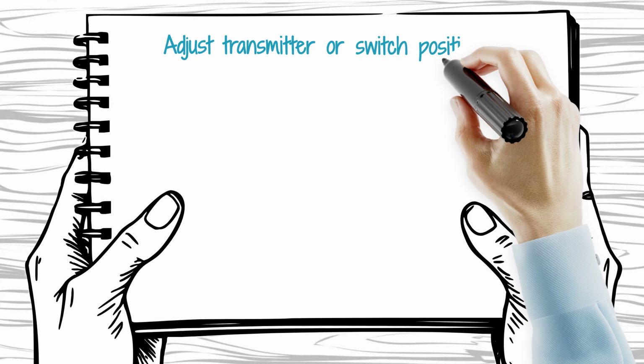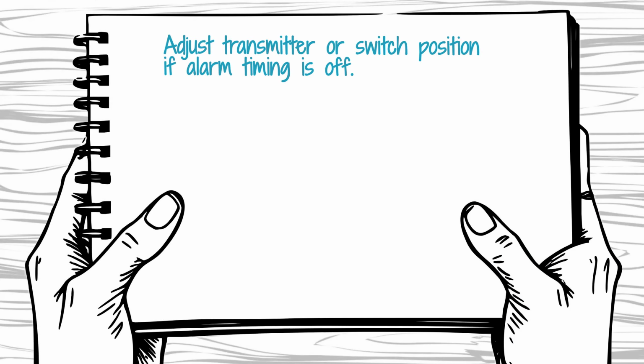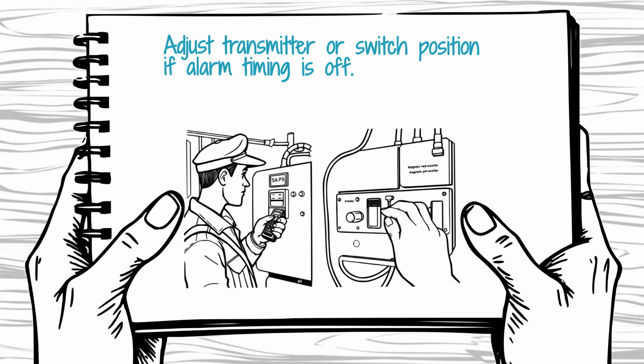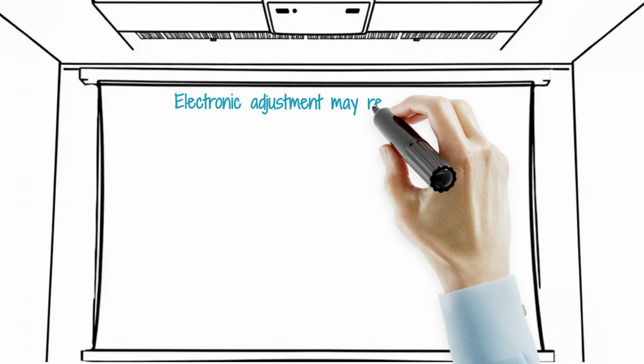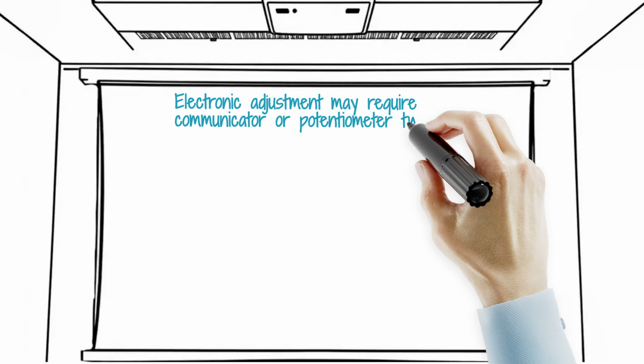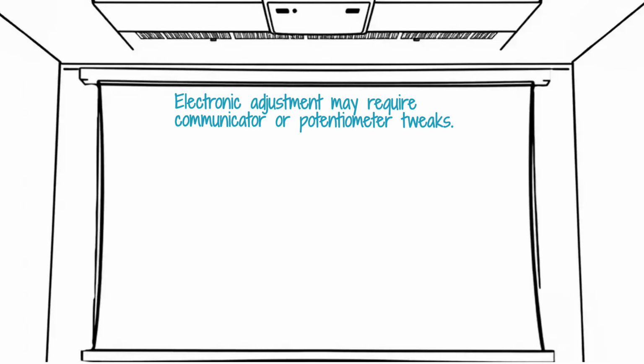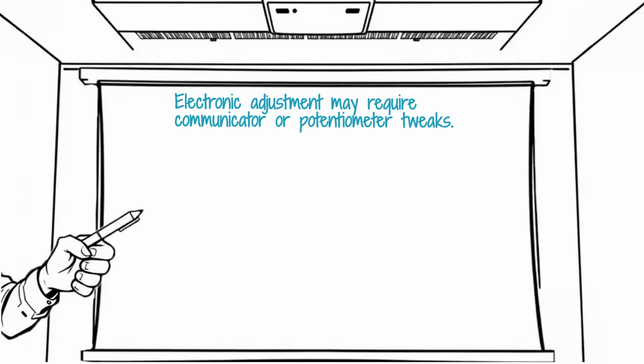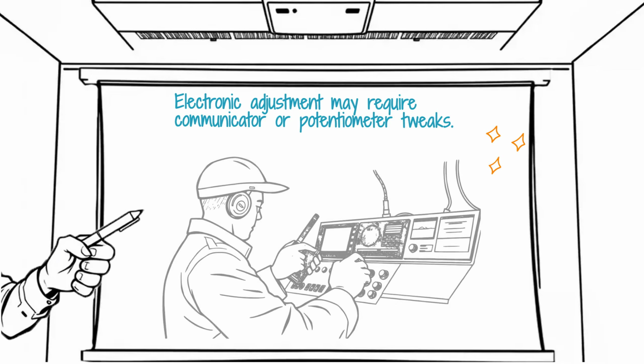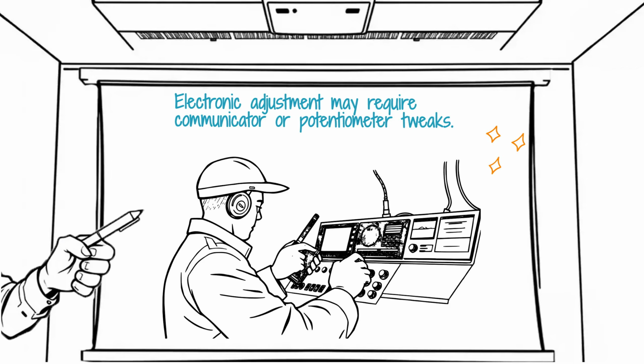If the alarm sounds too early or too late, you must adjust the zero and span settings on the transmitter or move the position of the magnetic reed switches. For electronic transmitters, this often involves using a handheld communicator or adjusting potentiometers to align the output signal with the physical water level. If the system uses a float with a mercury or micro switch, inspect the mechanical linkage for any signs of friction or salt deposits that could delay the trip.